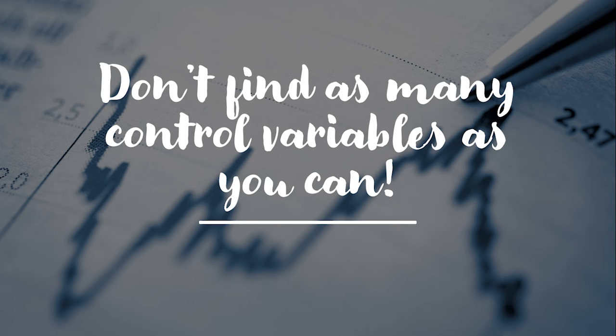I saw it here. Your vaporizer: your CV is outlet temperature, your MV is flow rate of steam, your DV is flow rate inlet and temperature of steam. But it will be constant, right? Constant, what constant? Temperature of steam, the inlet temperature of steam. We don't care about the outlet temperature of steam after it absorbs your heat and cools down.